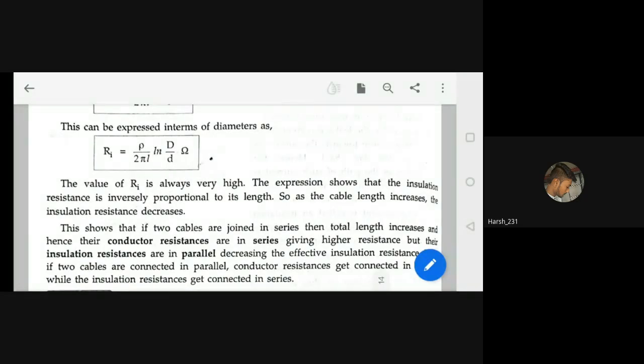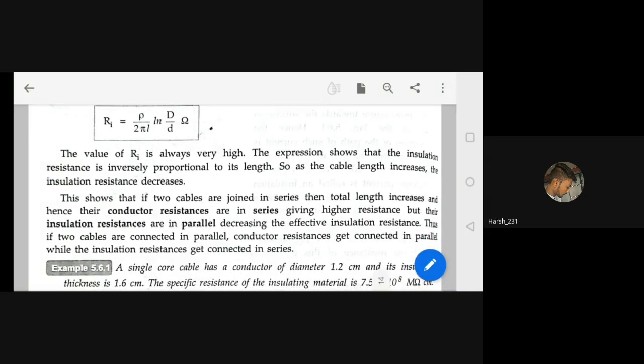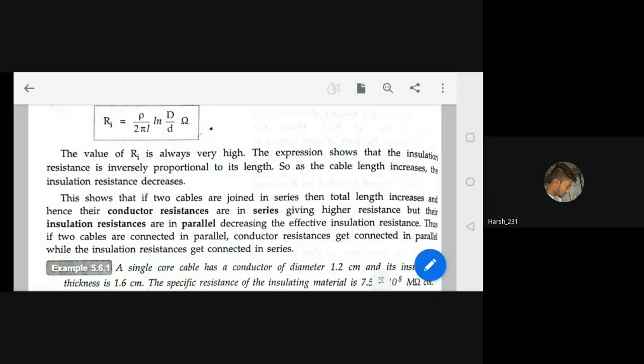If two cables are joined in series, total length increases, so conductor resistances add in series giving higher resistance, but insulation resistances combine in parallel, decreasing effective insulation resistance. Conversely, if two cables are connected in parallel, conductor resistances go in parallel while insulation resistances go in series. Conductor resistance and insulation resistance do not behave the same way.